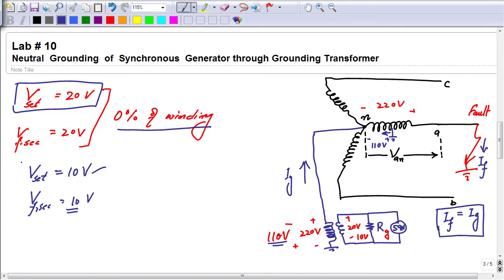But if we reduce the voltage to 10 volt, then yes, all the faults from the terminal of this winding up to the midpoint would be detected by the relay. But if the fault moves from the midpoint towards the neutral, a fault anywhere across this portion would not result in sufficient voltage across this grounding resistance to be detected by the relay, because its setting is equal to 10 volt. So that fault would not be detected.